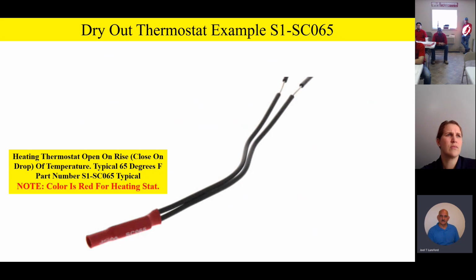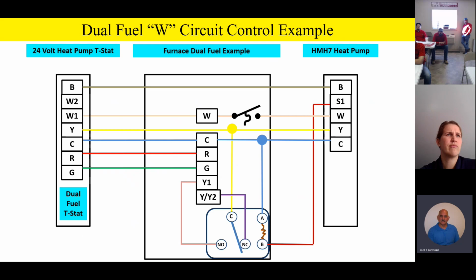And then you're going to wire tie that little thermostat to the suction line on the evaporator coil, which is a hot gas line. Remember, on a heat pump, it's a hot gas line in the heating mode. But you're going to wire tie it and insulate it to the suction line on the evaporator coil. And then what'll happen, here it's wired in the circuit. As long as that line is warm from the previous heat pump cycle, that thermostat will be open electrically. And so on the next call for heat, it's not going to bring the furnace on or cause the furnace to run for like 1 minute the next time it goes into heating mode. Because remember, the outdoor unit's designed to bring the heating on inside for about 1 minute, just to kind of preheat the air so you don't have a cold blow complaint.